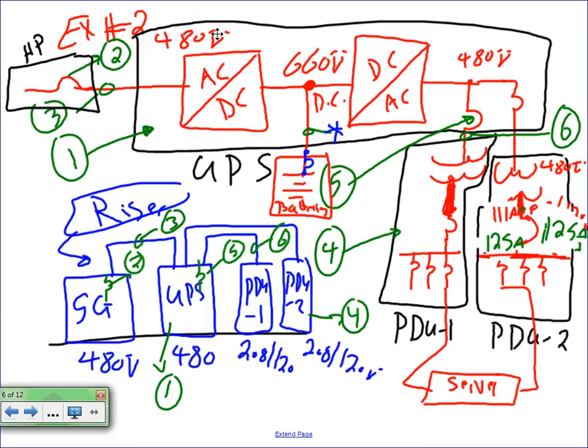Did we look at the batteries? Some of you haven't seen the batteries yet. When we go to Allianz, guys, you're going to see exactly what we're looking at. So here's a UPS, a big box. Inside the box, there's a conversion mechanism that converts AC to DC. At the DC level, they tie a bank of batteries, a room like this, in series and parallel, and they take 2 conductors, positive and negative, and tie them right into the UPS system.